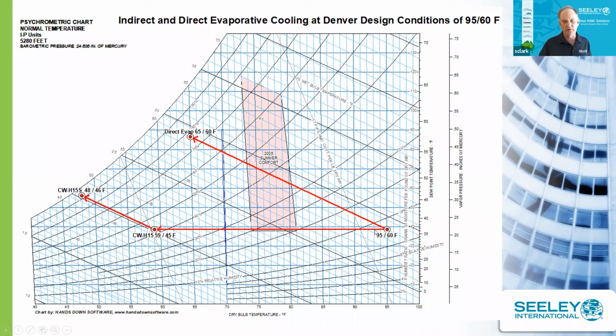We also know our indirect evaporative coolers called the Climate Wizard units, which start out at the same 95/60 design conditions, do sensible cooling down here to about 59 degrees. Notice this is 1 degree below the wet bulb. And so these are basically our most basic indirect evaporative coolers.